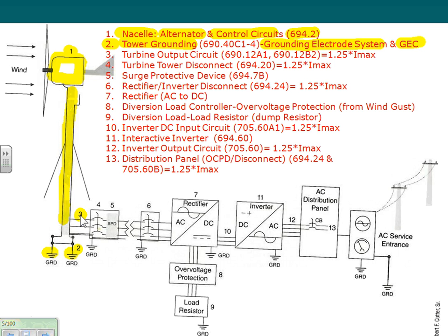If you see now number 3 right in here, now we're grabbing wires out of that turbine, right? Now we got captured wires. They call these wires the output circuit. I did this for the electricians only. If you don't believe me, this is where you can find this information. Being master electricians, the first thing when we install a system, we care about how big of a conductor do I need, what type of conduits, what type of disconnects, and what type of overcurrent protection device. That's our job.